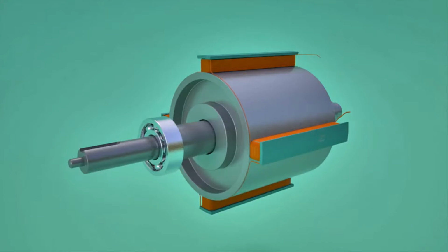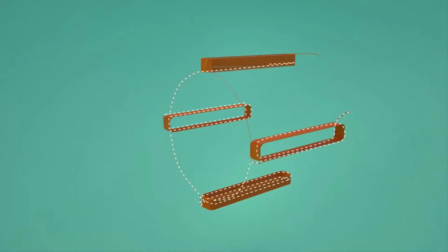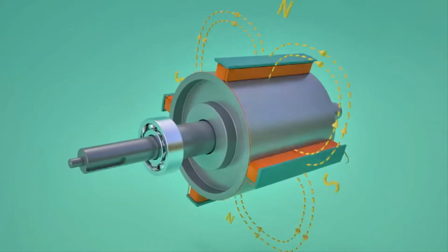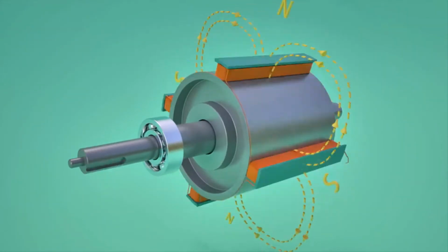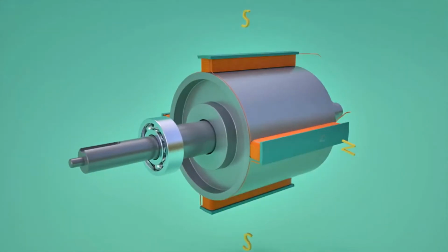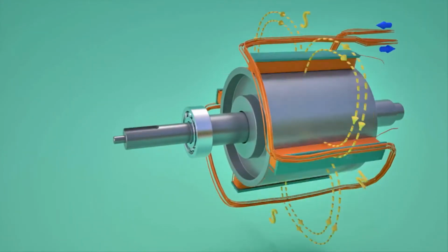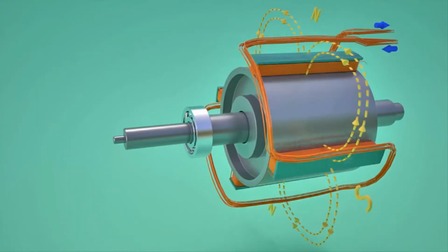The kind of rotor shown here is known as a salient pole rotor. For better insight into its working, let's consider a rotor with just 4 poles. The rotor coils are excited with a DC power source. The rotor is made to rotate by a prime mover. This makes the rotor flux also rotate along with it at the same speed. Such revolving magnetic flux intersects the armature coils fitted around the rotor. This generates an alternating electromotive force across the winding.